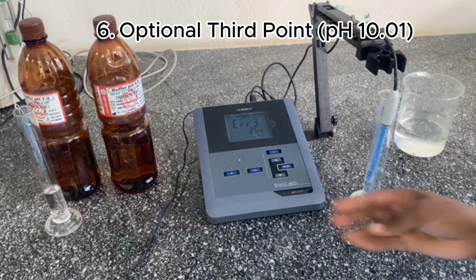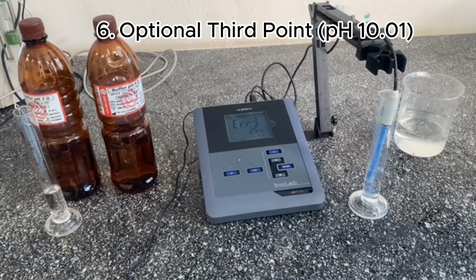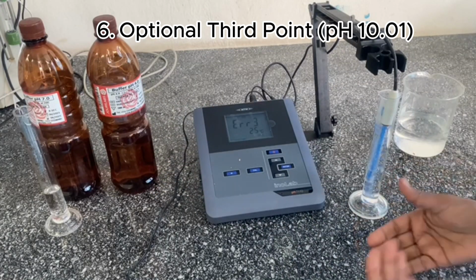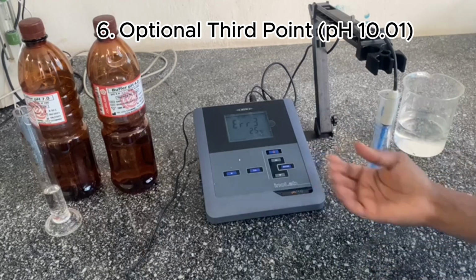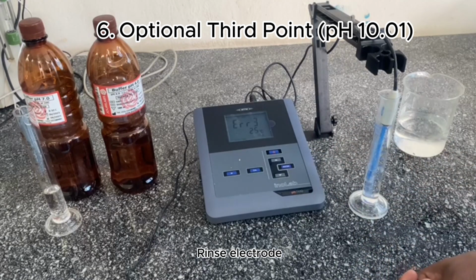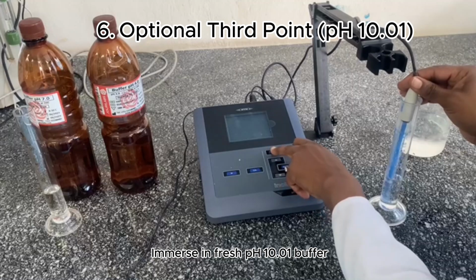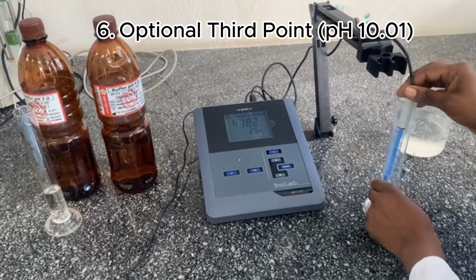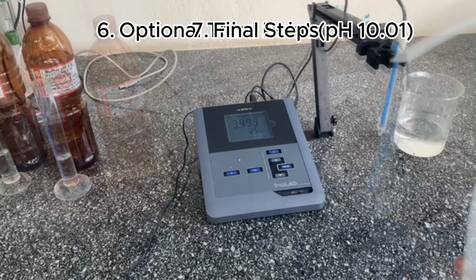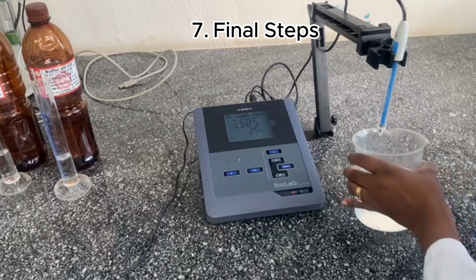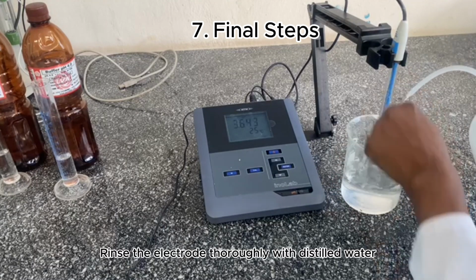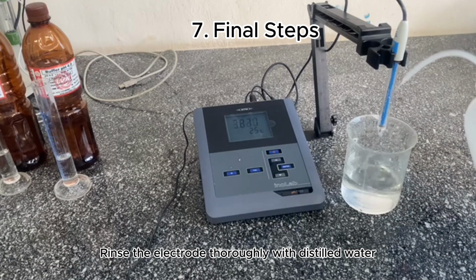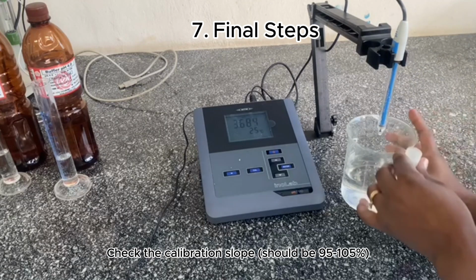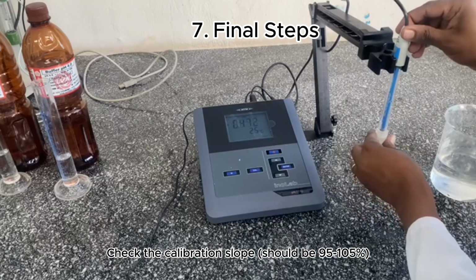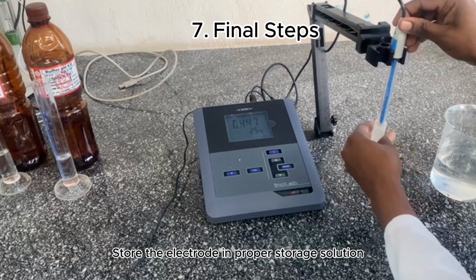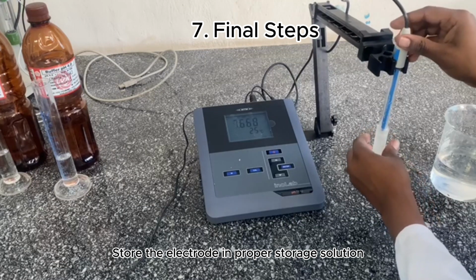6. Optional third point, pH 10.01. If using pH 10.01 buffer, repeat the process. Rinse electrode. Immerse in fresh pH 10.01 buffer. Calibrate and confirm. 7. Final steps. Rinse the electrode thoroughly with distilled water. Check the calibration slope, should be 95 to 105%. Store the electrode in proper storage solution.